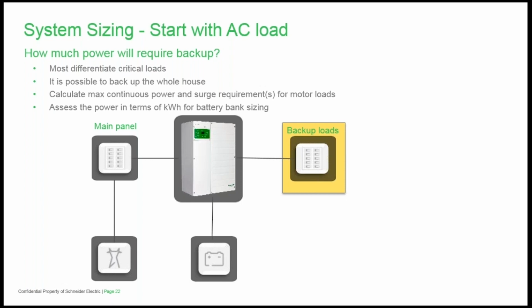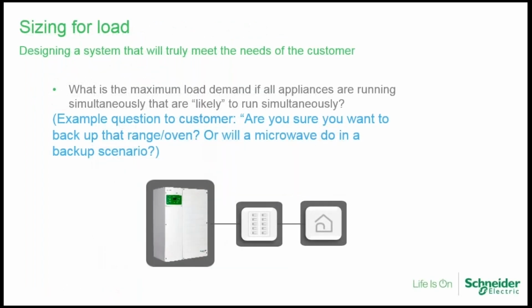Assess the power in terms of kilowatt hours for battery bank sizing. Whether designing an AC coupled system for new construction or as a retrofit, it's important to understand how the system will be used and follow certain basic sizing guidelines. We always start with the AC load. This is how to size the inverter charger system.